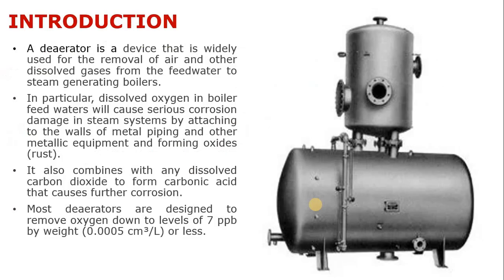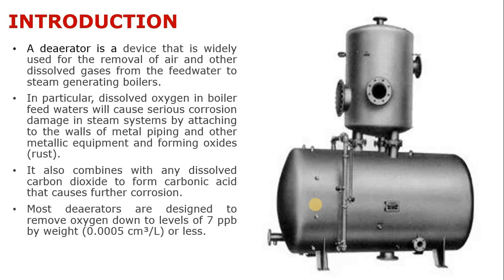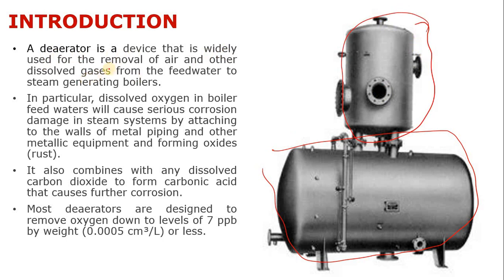Now let's look at what a de-aerator looks like — there is one vessel with another vessel at the top. A de-aerator is a device widely used for the removal of air and other dissolved gases from feed water to steam-generating boilers. Dissolved oxygen in boiler feed water causes serious corrosion damage by attaching to the walls of metal piping and other metallic equipment, forming oxides like ferric oxide.